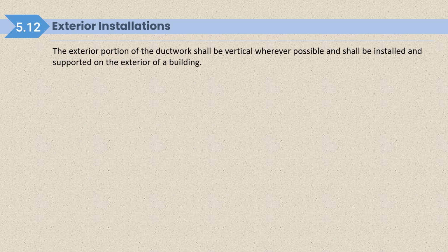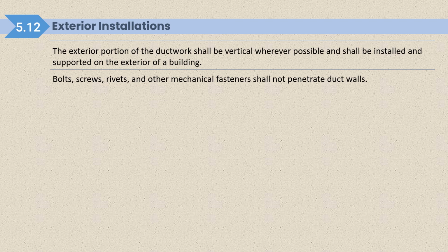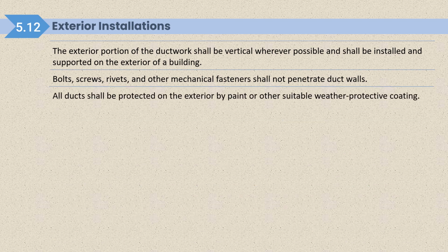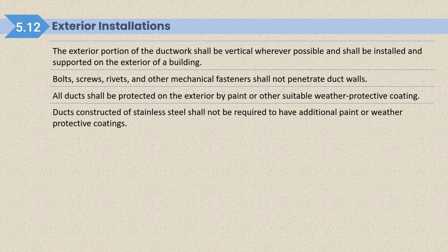Exterior installation: the exterior portion of ductwork shall be vertical wherever possible and shall be installed and supported on the exterior of a building. Bolts, screws, rivets and other mechanical fasteners shall not penetrate ductwork. All ducts shall be protected on the exterior by paint or other suitable weather protective coating to prevent corrosion.